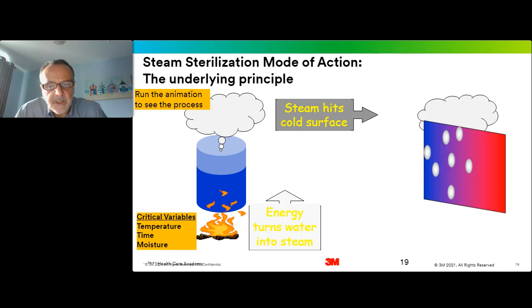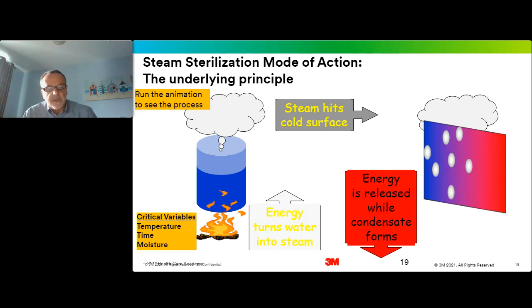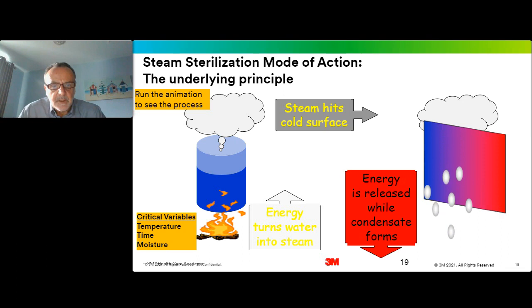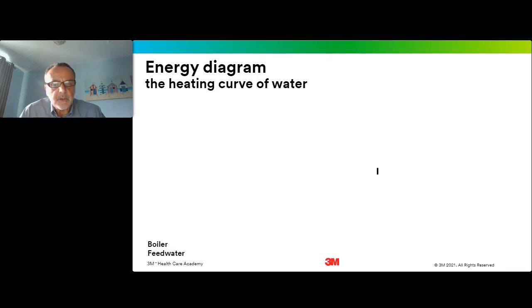And of course, at this point, if the steam contains any contamination, then as it condenses on the surface of the load items, the stainless steel instruments, etc., it will deposit any contamination that's contained in the steam on those surfaces. So this is why we need to pay particular attention to our steam generation process in order to make sure that the quality of our steam is of an acceptable level. So I think what we now need to do is look at how the steam itself is generated and the points where contamination can occur in this sterilization process.